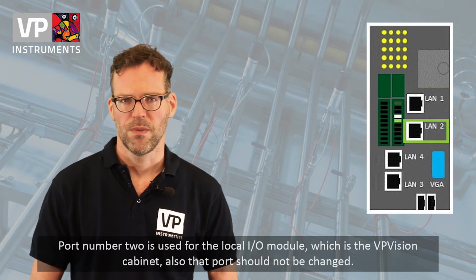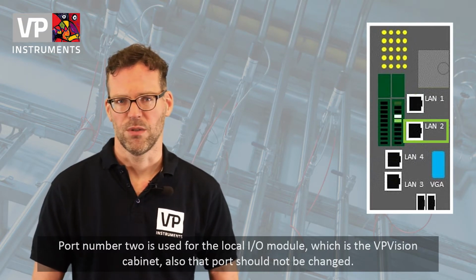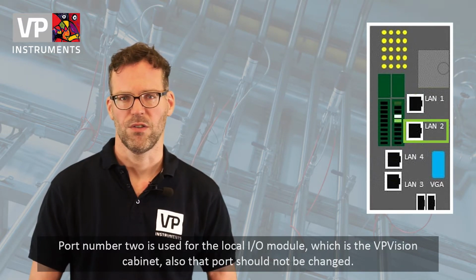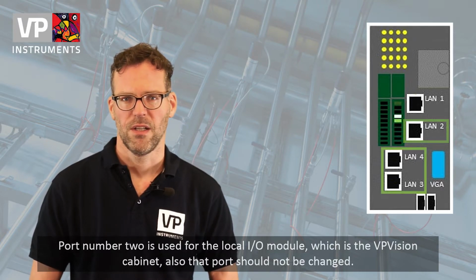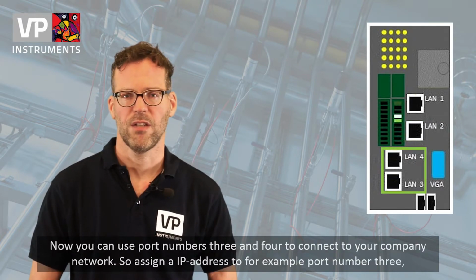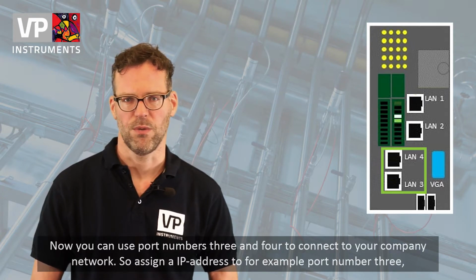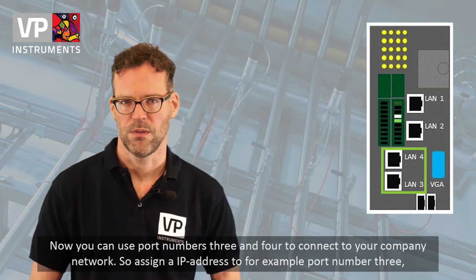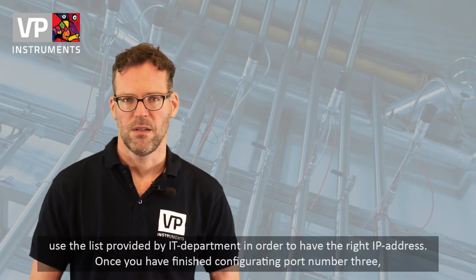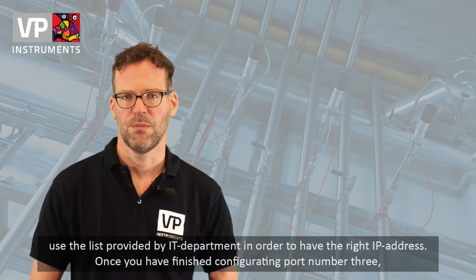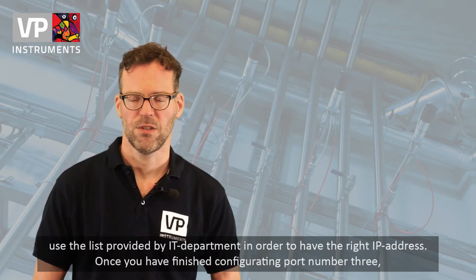Port number 2 is used for the local I/O module which is in the VPVision cabinet. Also that port should not be changed. Now you can use port number 3 and 4 to connect to your company network. So assign an IP address to, for example, port number 3. Use the list provided by the IT department to have the right IP address.